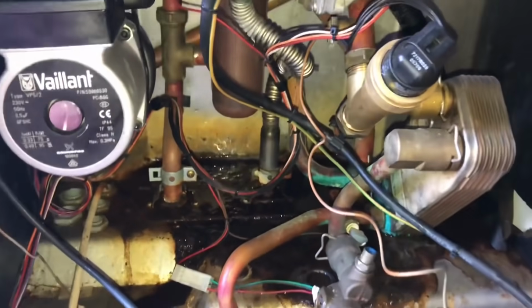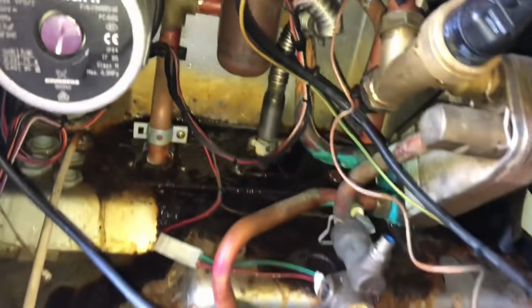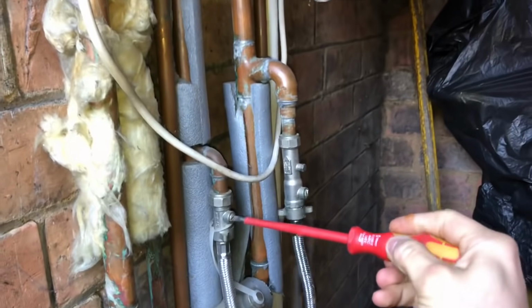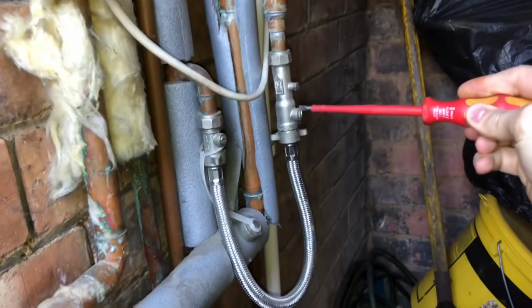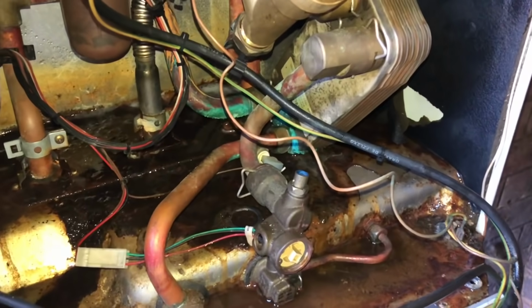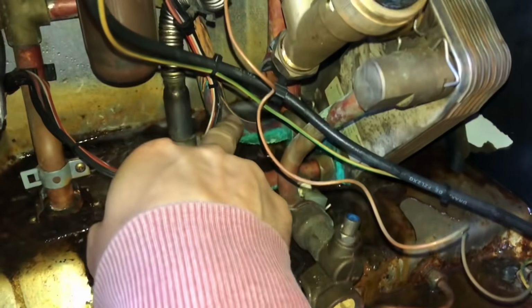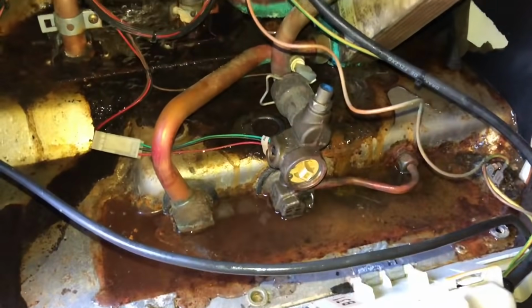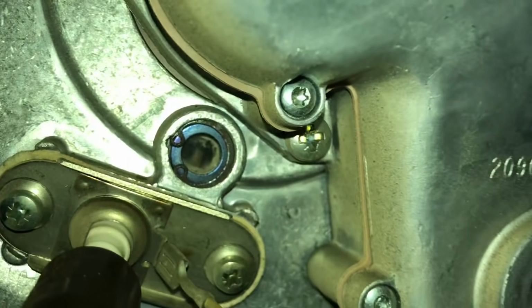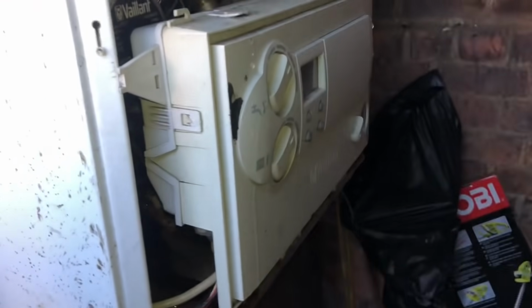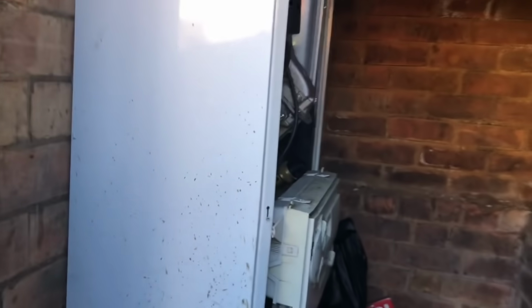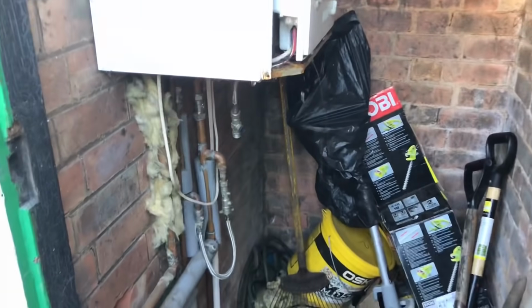So what I would normally do is I would suggest we see if that's a bit. Let me just turn the filling loop off first. That's just what it was. Yeah, so as I was saying, a lot of the time I would probably just source this part and repair it, but the condition the boiler's in, the fact that it's been leaking a while, it's probably not been serviced. Looks a bit dirty inside the heat exchanger, and just the age of it really. I mean, I will be quoting for a new boiler on this one.